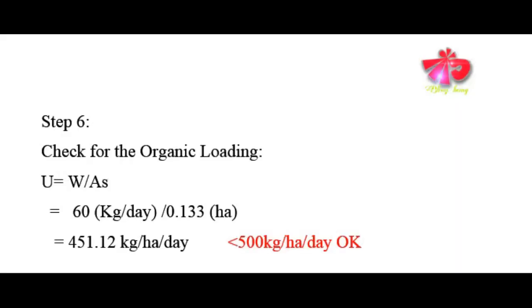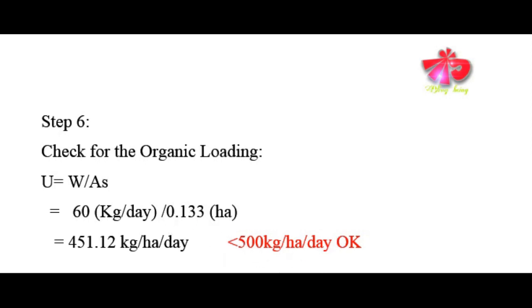In Step 6, we check the organic loading using u = W / surface area = 60 kg per day ÷ 0.133 hectares = 451.12 kg per hectare per day. This is less than the permissible value of 500 kg per hectare per day, so our revised surface area is acceptable.